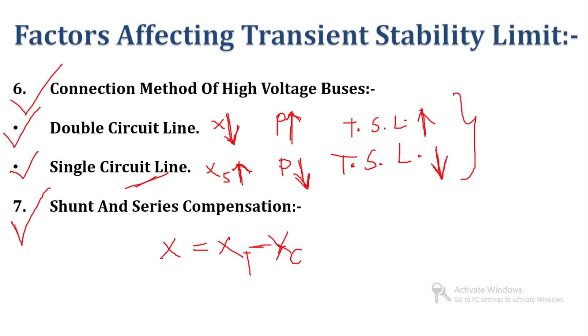So that is the sixth point. Now the seventh point is shunt and series compensation. As we all know, series compensation will reduce the net transfer reactance of the transmission line. Clear? If we add the capacitor bank in series with the line, it will reduce the overall reactance of the line. So if reactance reduces, power transfer capability will improve, and due to that the transient stability limit will also increase. So that is the effect of series compensation.